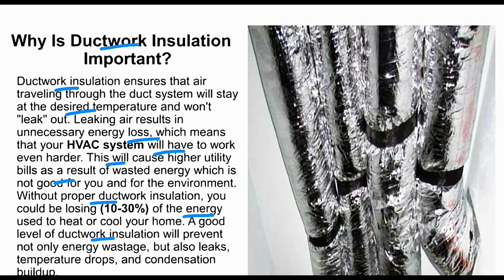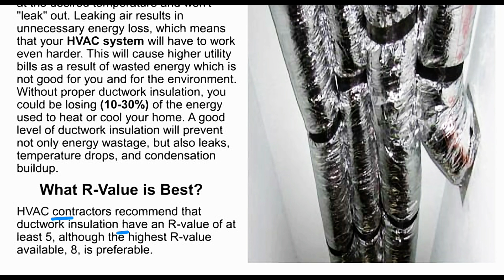Without proper ductwork insulation, you could lose 10 to 30% of the energy used to heat or cool your home. A good level of ductwork insulation will prevent not only energy wastage but also leaks, temperature drops, and condensation buildup. What R value is the best? HVAC contractors recommend that ductwork insulation have an R value of at least 5, although an R value of 8 is preferable.